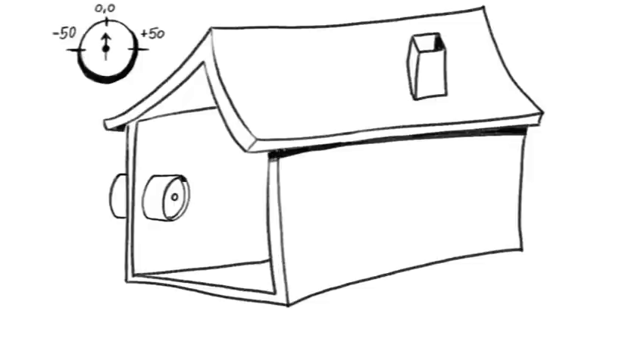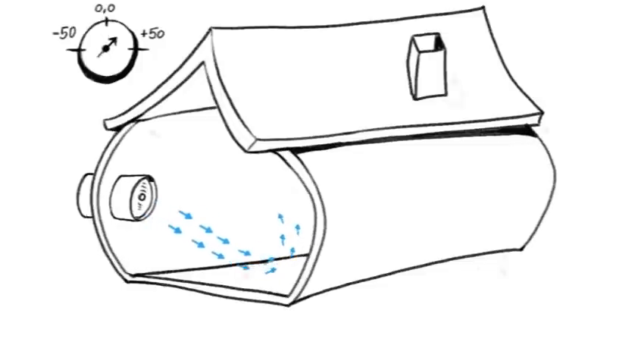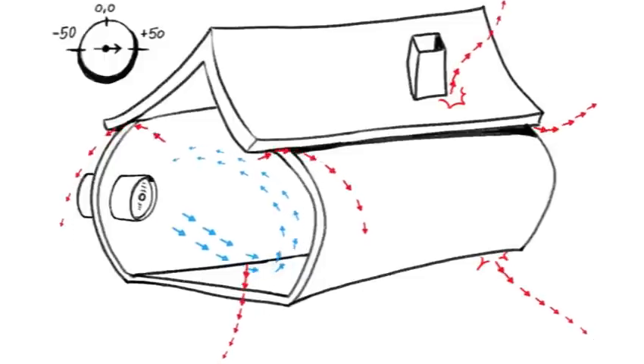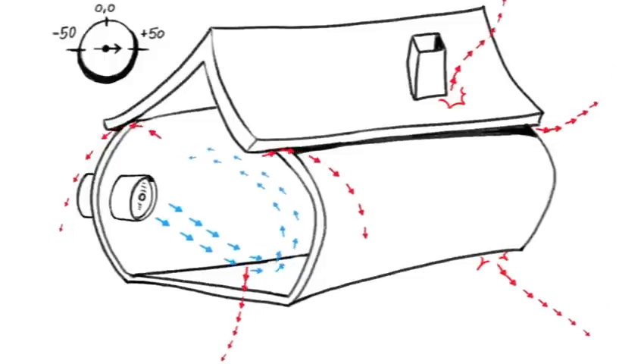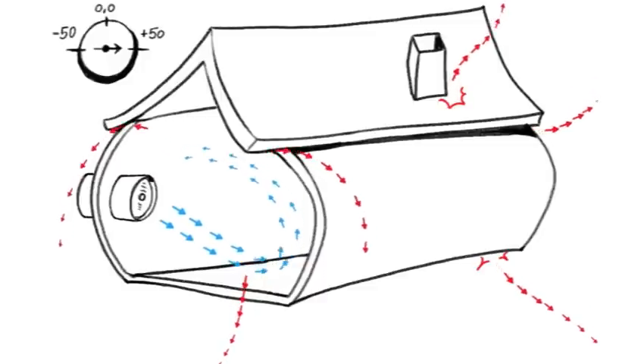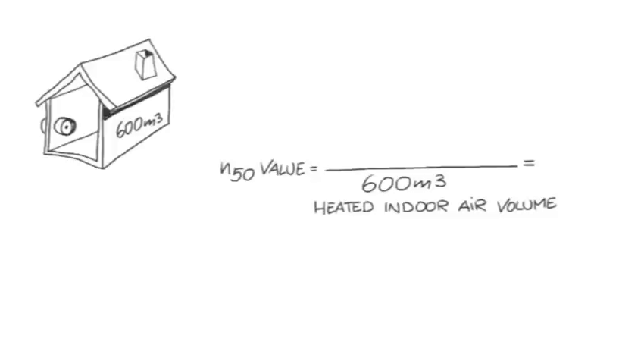Then the fan conveys outside air into the structure and generates a positive pressure of 50 Pascal. This corresponds almost to wind force 5. The more air escapes to the atmosphere through leaks, the more air must be conveyed by the fan and the higher is the air change rate, the N50 value. The value is indicated in the display. It is called V-leckage, volume flow through the leaks. This volume flow is determined for one hour.